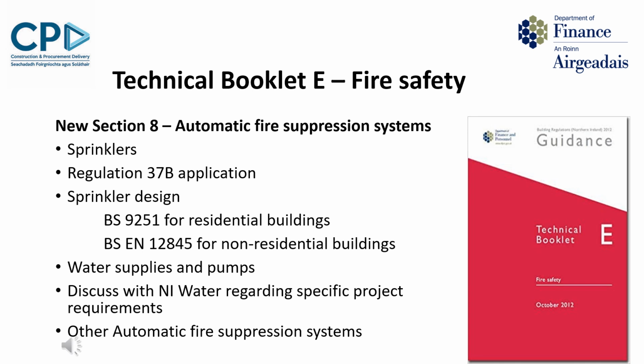For the design of sprinkler systems, the guidance makes reference to the up-to-date Code of Practice standards. So for residential buildings, it's BS 9251 of 2021, and that's the fire sprinkler systems for domestic and residential occupancies. And for non-residential buildings or residential buildings outside the scope of BS 9251, then it's BS EN 12845 of 2015, fixed firefighting systems, automatic sprinkler systems, design, installation and maintenance. The old standard BS 5306, fire extinguishing installations and equipment on premises, is no longer cited in Technical Booklet E.